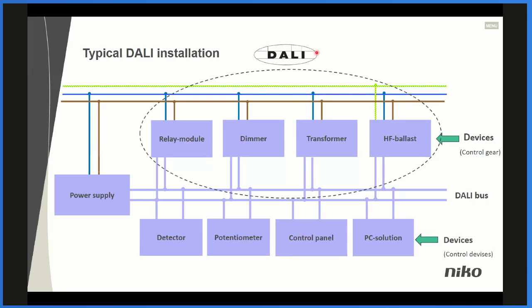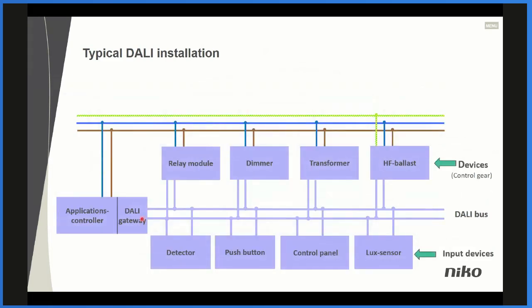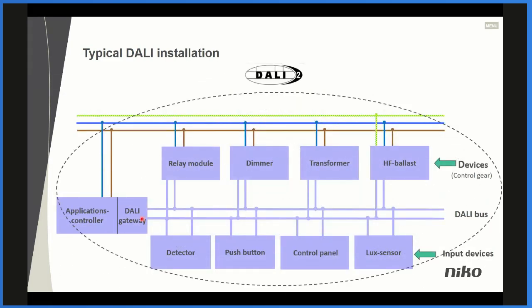And this is the logo of DALI. It kind of symbolizes a globe, and we have the DALI in the 4 letters you have, in order to say, okay, this is a global standard that you can have. But as time evolved, we said, why don't we have the control devices in the same standard as the control gear connected to the mains? That work has been going on for years now. And now we have the DALI 2 standard in place.